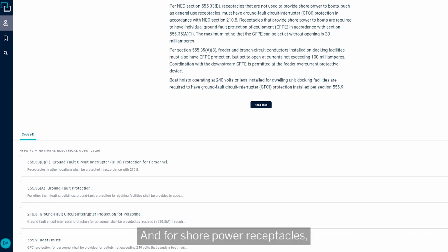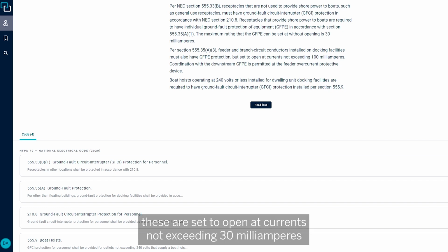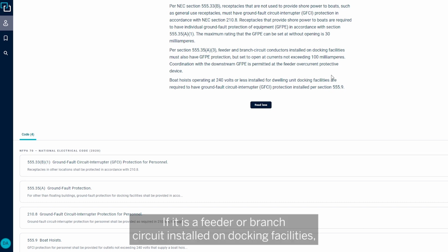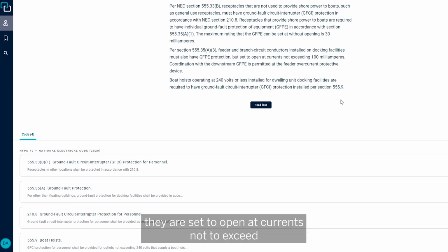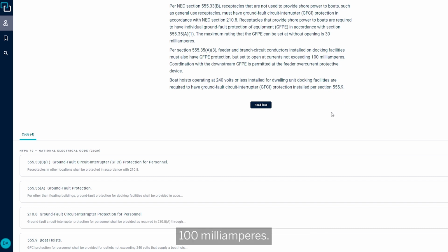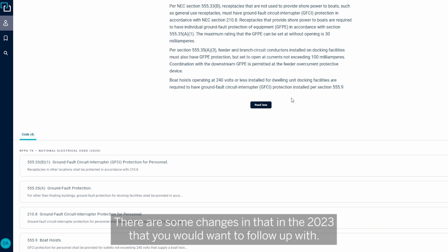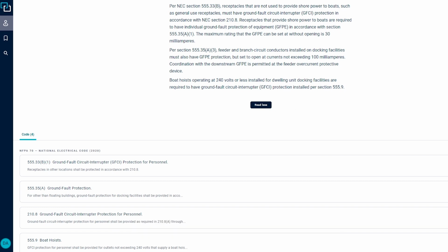555.35A3. For shore power receptacles, these are set to open at currents not exceeding 30 milliamperes. If it is a feeder or branch circuit installed on docking facilities, they are set to open at currents not to exceed 100 milliamperes. So it just depends on what they're feeding. There were some changes in that in the 2023 code that you would want to follow up on.